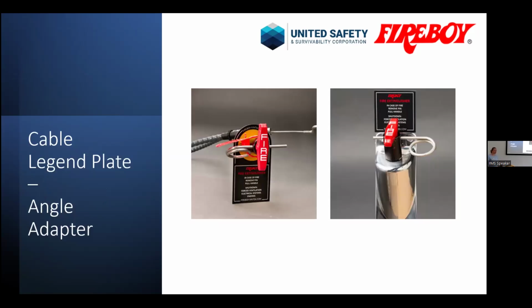This is the manual pull cable that comes as a secondary option, or if you're doing a manual only activation, that's the only option of activating your fire extinguishers by pulling the manual pull cable. The fire handle or the activation handle is normally mounted somewhere outside the space. Most of the time, helm, flybridge. If you have a small control or navigation bridge, it could be mounted there. The pull cables come in different lengths. There is an inner, very thin stainless steel cable within the rubber heat protective sheath. So you're just basically pulling on the inner pull when you pull the handle.